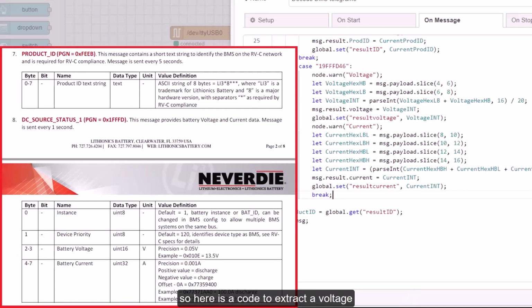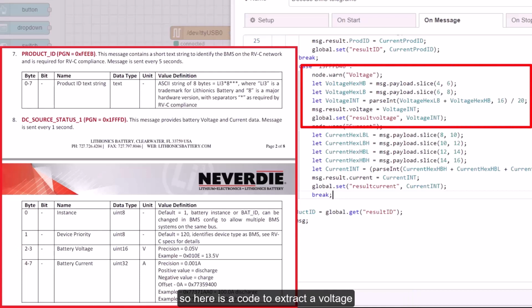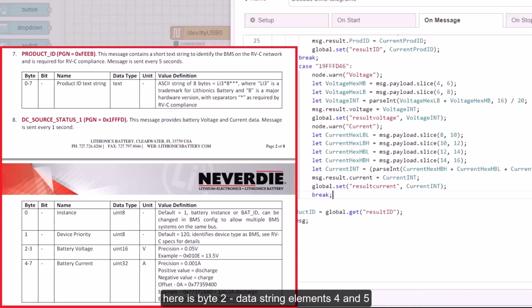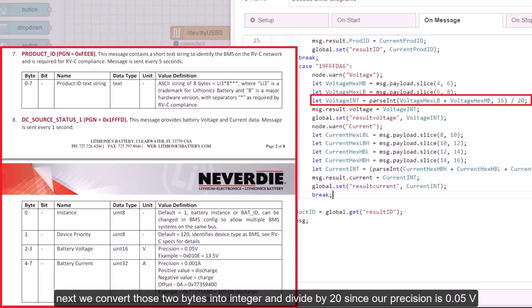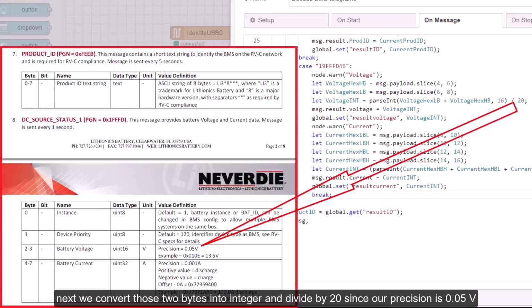First, we'll look into message data definitions - battery voltage is represented by bytes 2 and 3 of our data. Here is the code to extract the voltage: byte 2 is data string elements 4 and 5, and byte 3 is elements 6 and 7. Next, we convert those 2 bytes into an integer and divide by 20, since our precision is 0.05 volt.